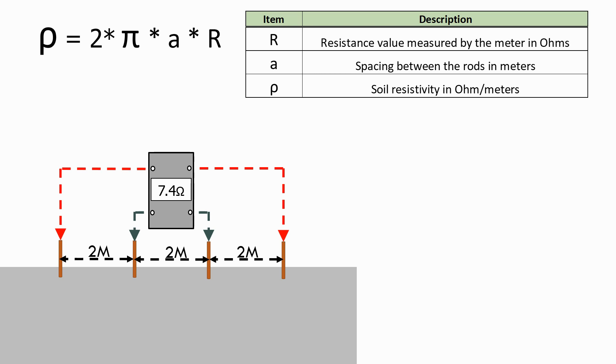As we can see on the meter, the value of R is 7.4 ohms and the spacing, A, is 2 meters, which will measure the soil resistivity at a depth of 2 meters. Let's now put these values in the formula, giving us a soil resistivity of 92 ohm meters at a depth of 2 meters.